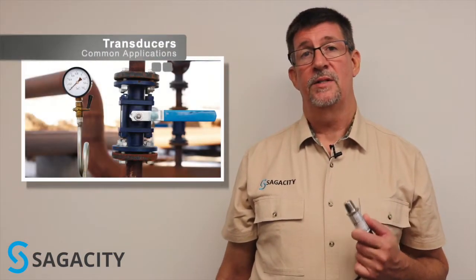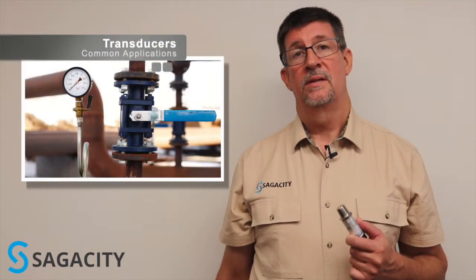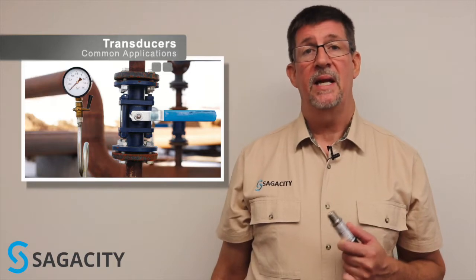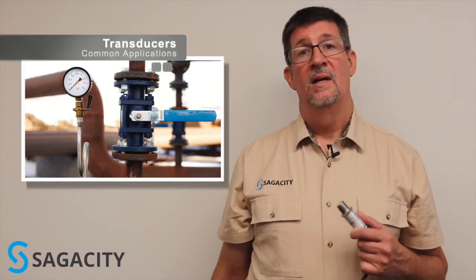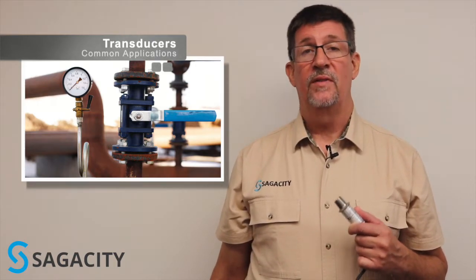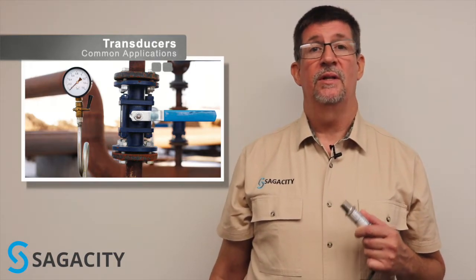Applications for transducers, which are typically a fixed range device, would be applications where you don't have process variables changing in the future. A lubrication skid, for example, where you know you have to have 40 or 50 pounds of pressure in order to keep the lubrication of your equipment going.